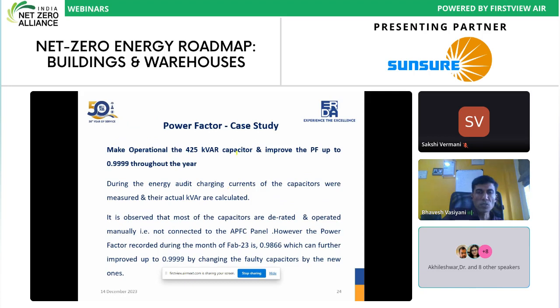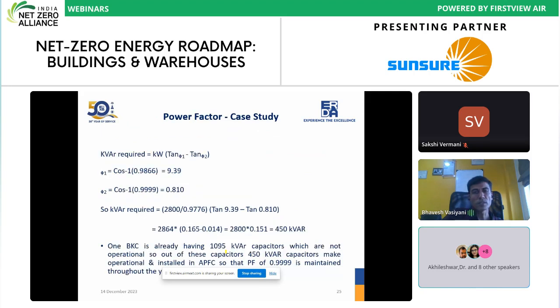Another area, which is a well-known area now and people are maintaining it, but this is the case of one building in Maharashtra where billing is in KVAR also being charged. So here they had capacitor banks, but some were not in operation, though they were operating at 0.9866 power factor. It is a very good power factor, but further improvement is still possible, until you reach 0.999 in the current scenario. So we suggested maintaining these capacitor banks and replacing some capacitors. So improvement in power factor or requirement of capacitors was suggested based on the formula. So APFC can give you up to 0.99 power factor.